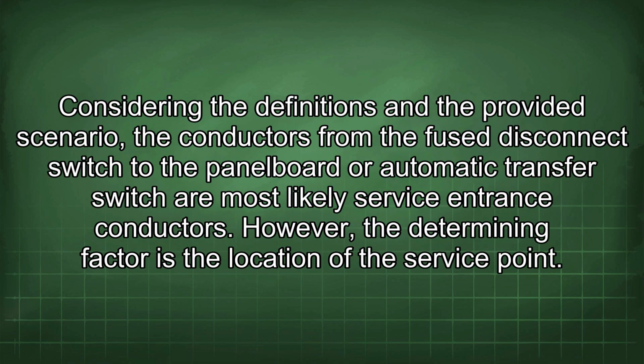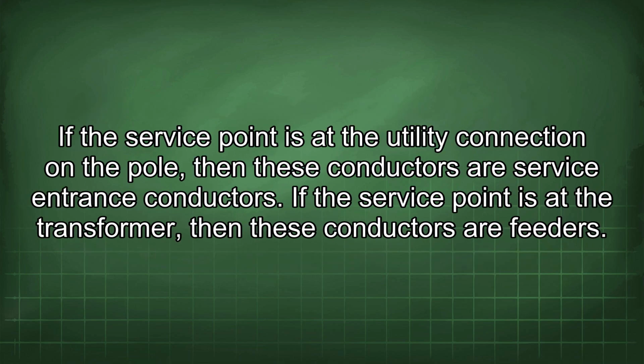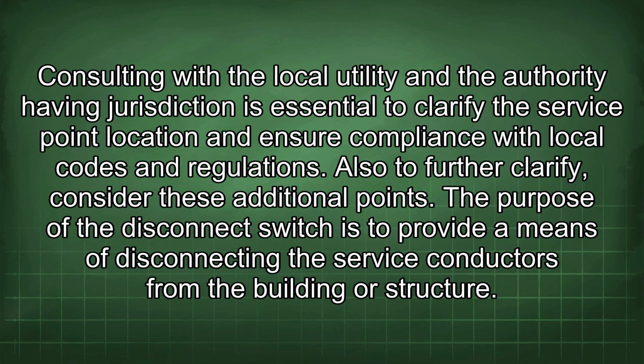Considering the definitions and the provided scenario, the conductors from the fuse disconnect switch to the panel board or automatic transfer switch are most likely service entrance conductors. However, the determining factor is the location of the service point. If the service point is at the utility connection on the pole, then these conductors are service entrance conductors. If the service point is at the transformer, then these conductors are feeders. Consulting with the local utility and the authority having jurisdiction is essential to clarify the service point location and ensure compliance with local codes and regulations.